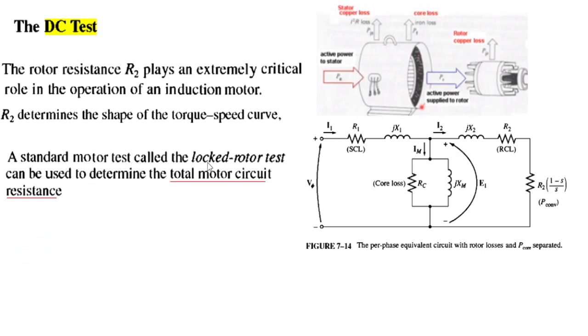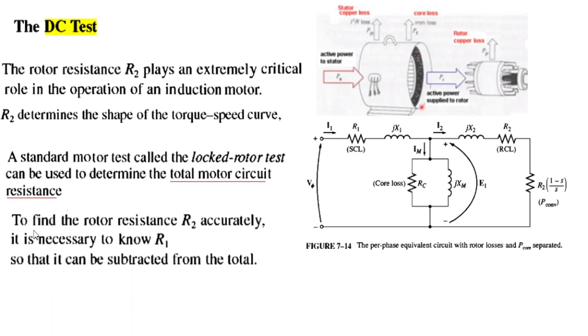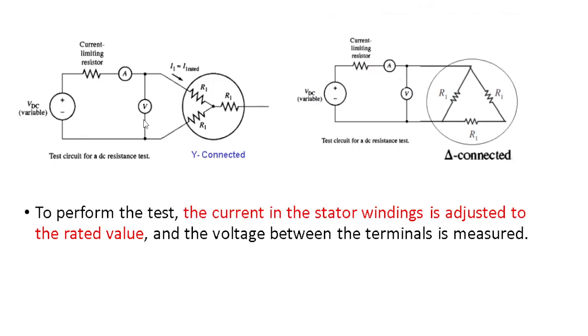A standard motor test called the locked rotor test can be used to determine the total motor circuit resistance. Once we know the total resistance and R1, we can calculate R2. To find the rotor resistance R2 accurately, it is necessary to know R1 so that it can be subtracted from the total.